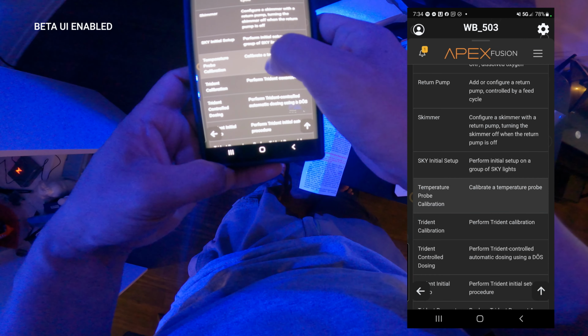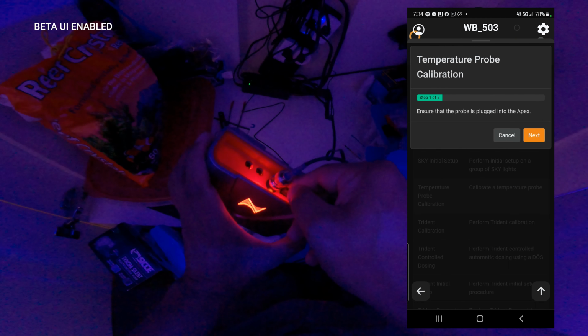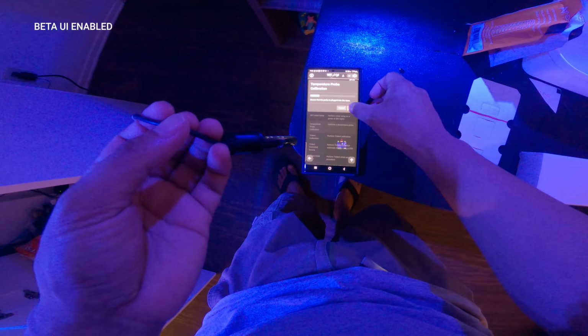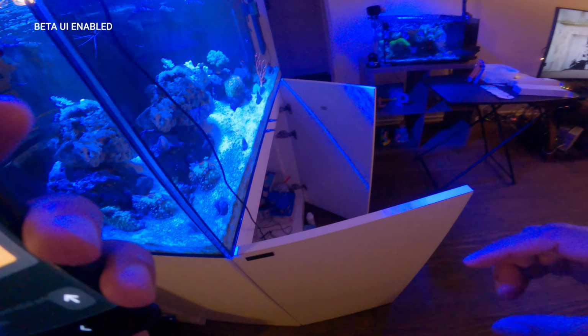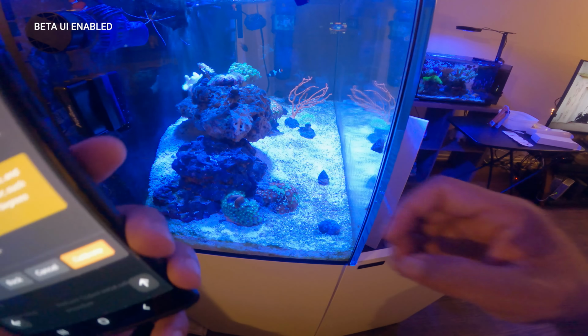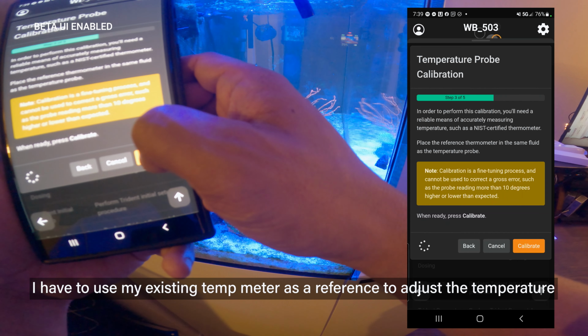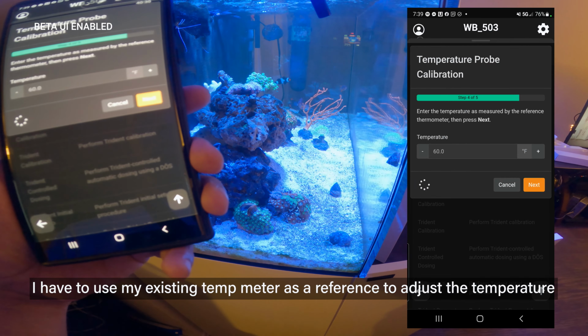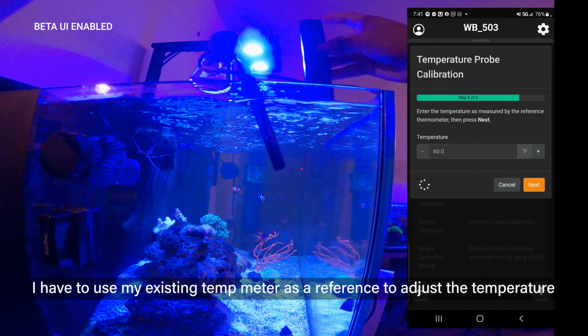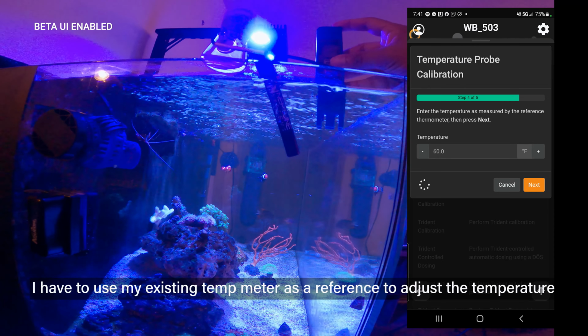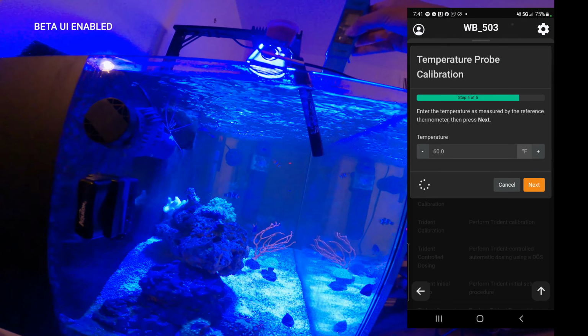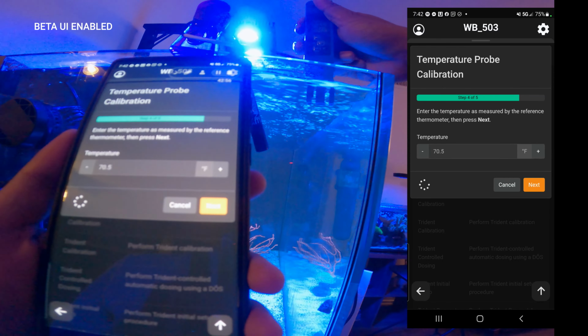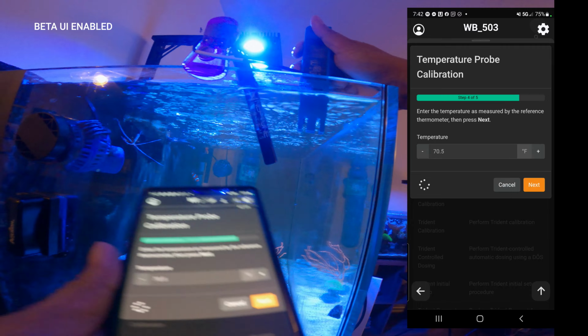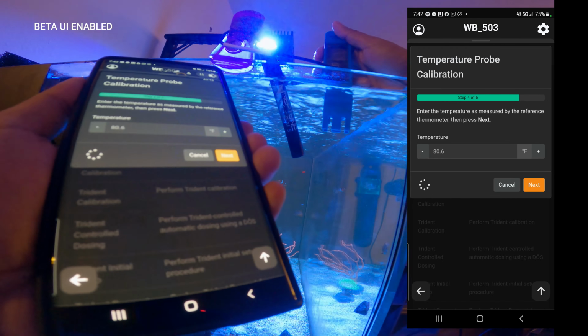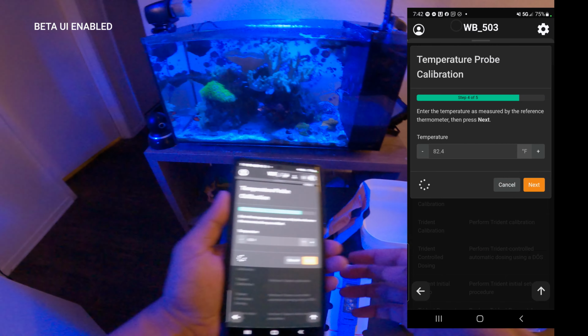For temperature probe calibration, go to Task and select Temperature Probe Calibration. Go ahead and connect your temperature probe to your Apex Junior. When ready, tap Next. In this step, you need a reliable temperature reader to match it with your Apex temperature probe. When you're ready for the reading, tap Calibrate. You can match and adjust the temperature by tapping the plus and minus button. Once you're done adjusting the temperature, just hit next and tap done.